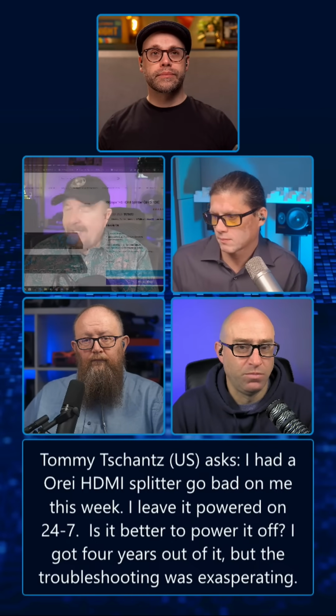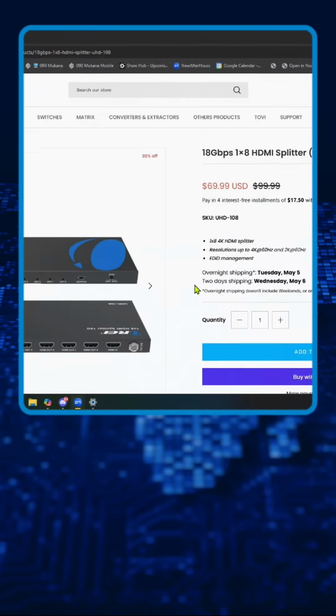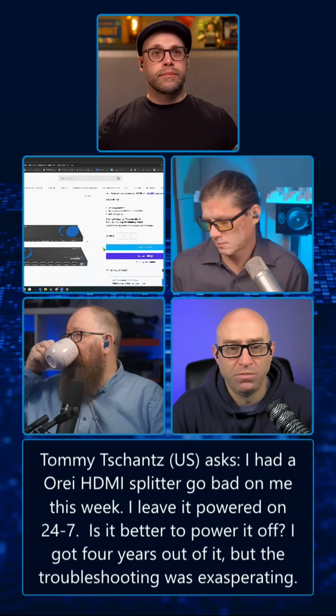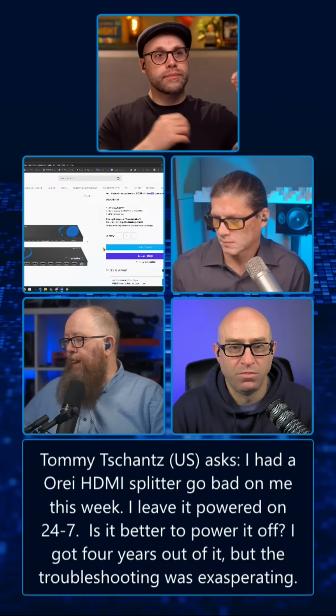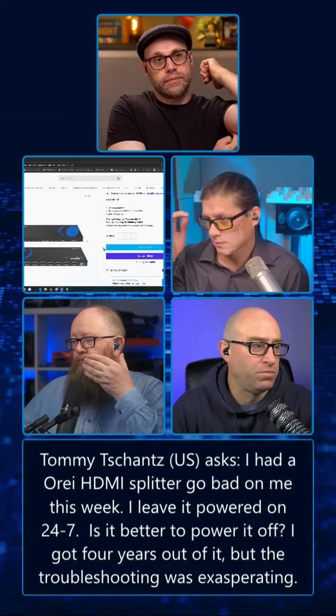Courtney, I don't know which one you had. I was looking at these 1x8s. I'd look at the power supply. If the power supply failed, it may be an easy fix. Just get a new DC power supply for it. If the power supply is good and supplying plenty of current at its required voltage, I think 12-volt, whatever the voltage input is on that power supply, then it's cheaper. These things are not very expensive. I think this one is $70 for a 1x8.